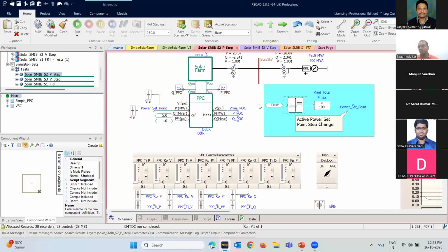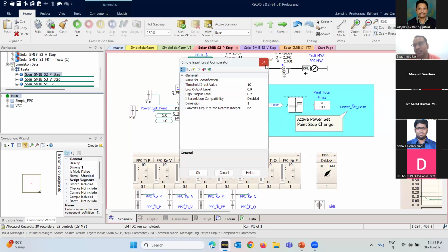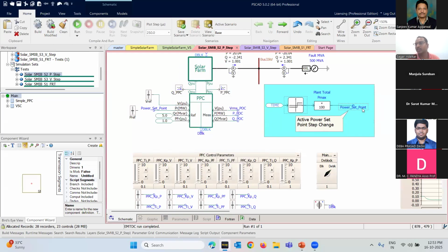Similarly, there are other ways to do this. This is not the only way. There are others. There's what we call sequences, which we can use to generate those time varying set points. And then this is a gain function. It is basically scaling the power output. If you see, this set point is required in megawatts, and here I'm providing it in per unit, so I have to multiply it by 100 so that the set point reaches the active power.